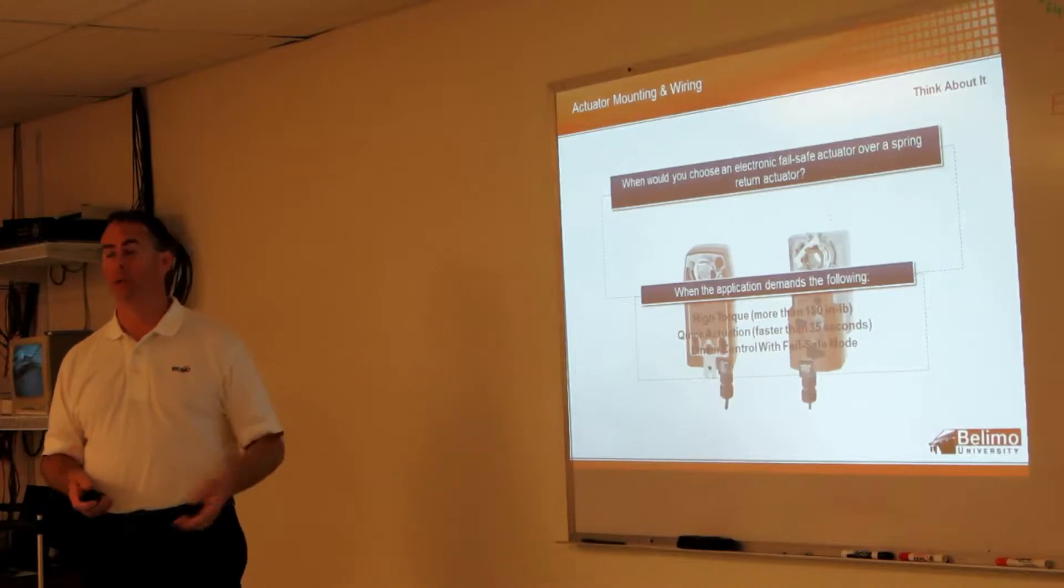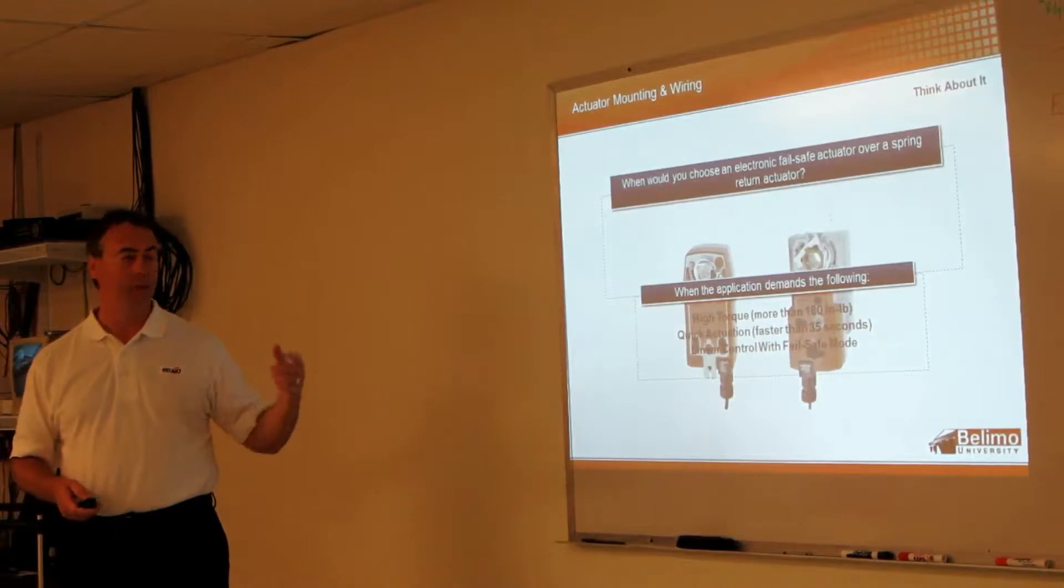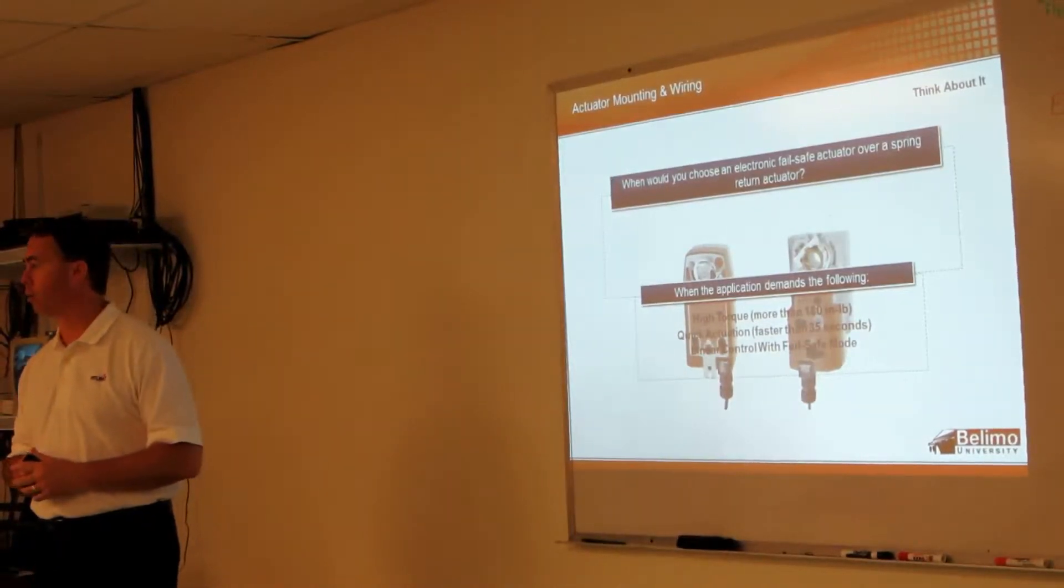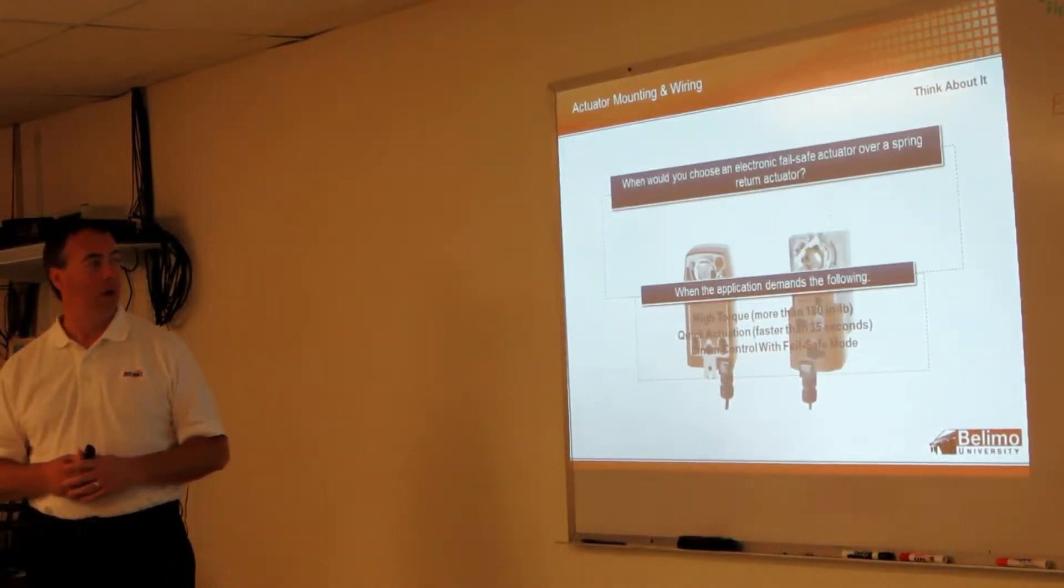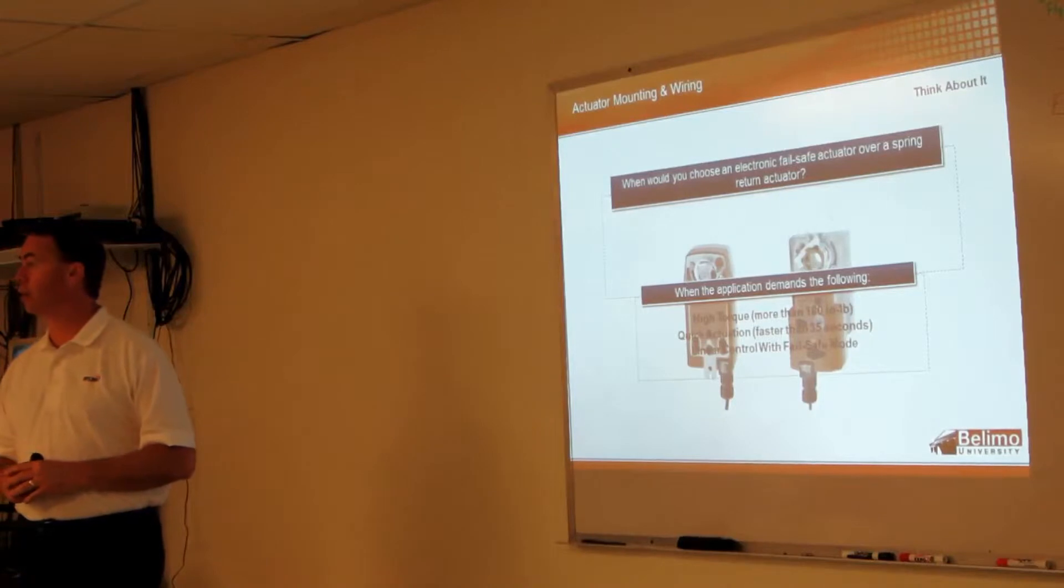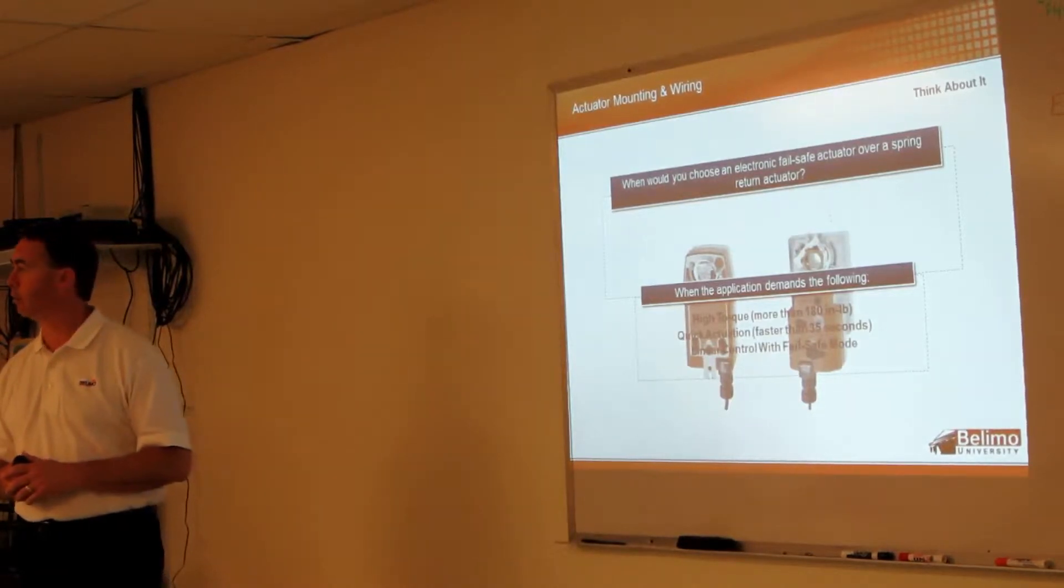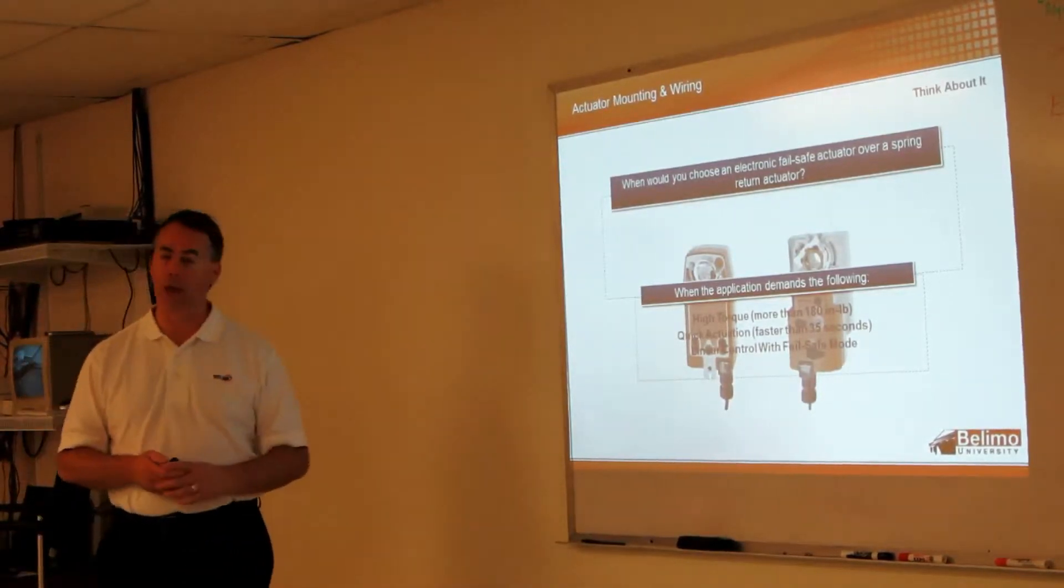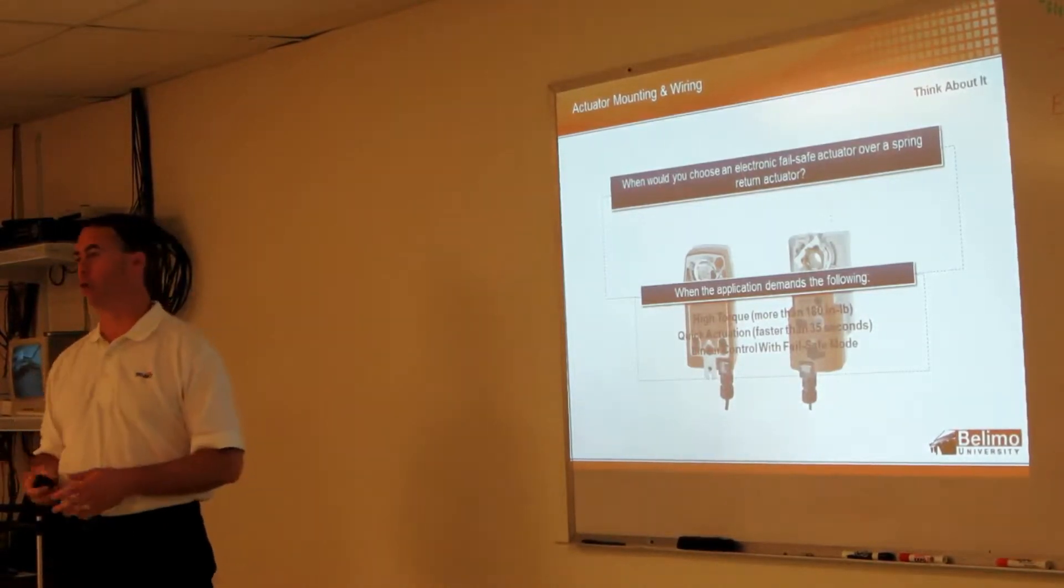Quick actuation. With the electronic fail-safe, you can program those for quicker actuation than you can with the spring return models. Or as I mentioned earlier, linear control. If you need a fail-safe with the linear actuator, which I was saying is good for pneumatic retrofits, like I said earlier, we don't have a spring return model for that, but we do have the electronic fail-safe. So those are a few of the applications where electronic fail-safe would be chosen over a spring return.